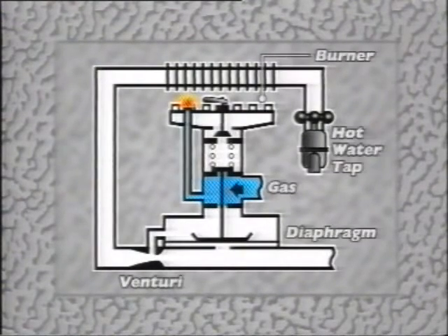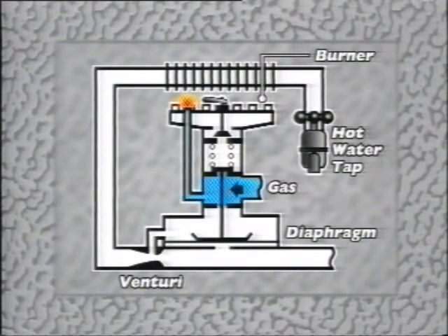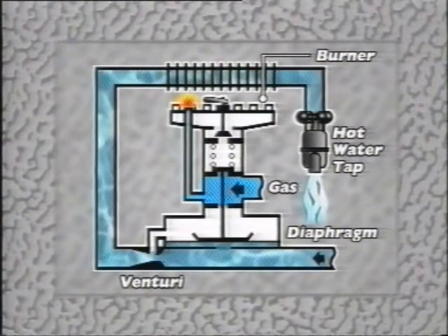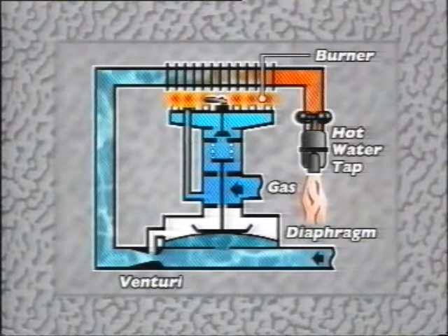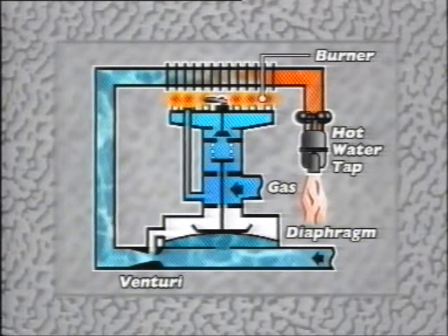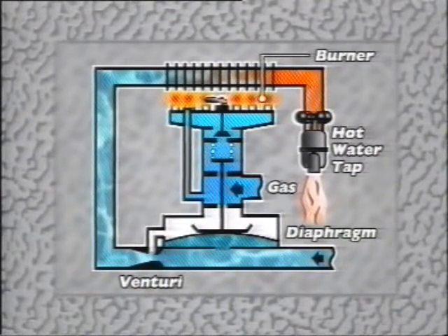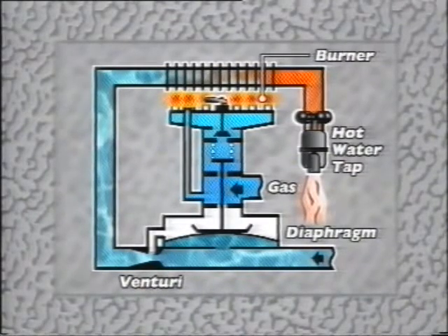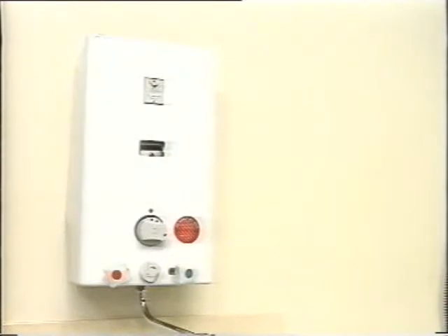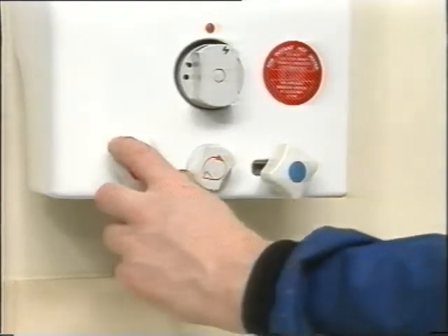So how does it work? Well, when there's no water flowing, the pressure on each side of this rubber diaphragm is equal. When the tap's turned on, water flows through the venturi, and as the flow increases, pressure at the throat of the venturi is reduced. As a result of that, the pressure above the diaphragm is reduced, and it's pushed upwards. It moves the bearing plate, which in turn lifts the gas valve, and the gas can flow. If the pilot's lit and the flame safety device is open, gas flows to the burner, gets lit by the pilot, and heats the water.